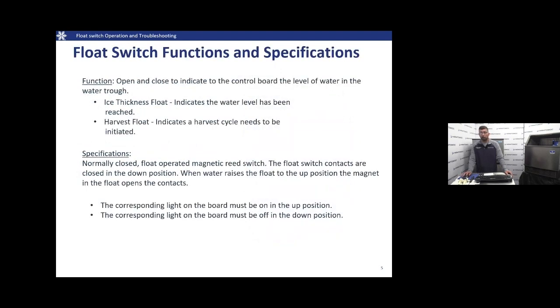The function of our float switches: they open and close to indicate to our circuit board the level of the water in the trough. The ice thickness float indicates that the water level we need to make a batch of ice has been reached. The harvest float indicates a harvest cycle needs to be initiated once that water drops below that float. Specifications: normally closed. The float operates as a magnetic reed switch. The float switch contacts are closed in the down position. When water lifts that float to the up position, the magnet in the float opens the contacts. The corresponding lights on the circuit board should be on when the float is up and should be off when the float is down.